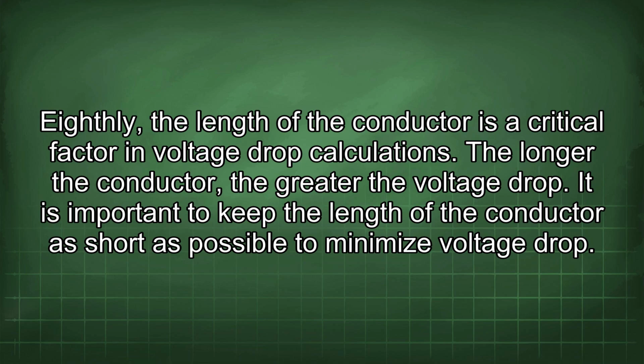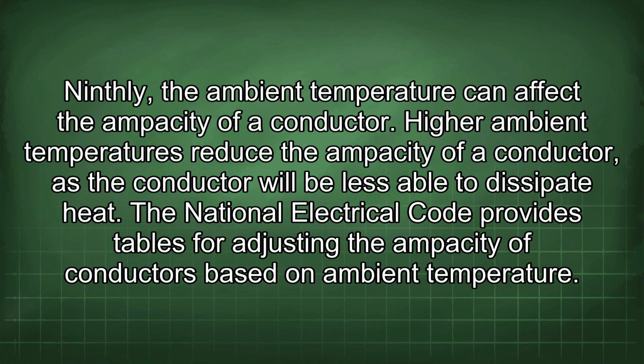It is important to keep the length of the conductor as short as possible to minimize voltage drop. Ninthly, the ambient temperature can affect the ampacity of a conductor. Higher ambient temperatures reduce the ampacity of a conductor, as the conductor will be less able to dissipate heat. The National Electrical Code provides tables for adjusting the ampacity of conductors based on ambient temperature.